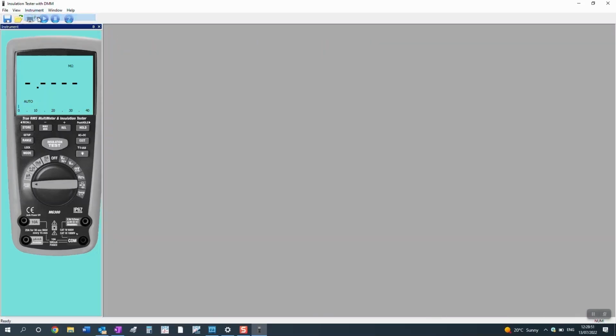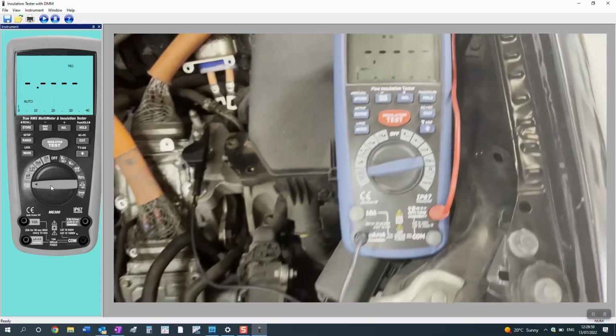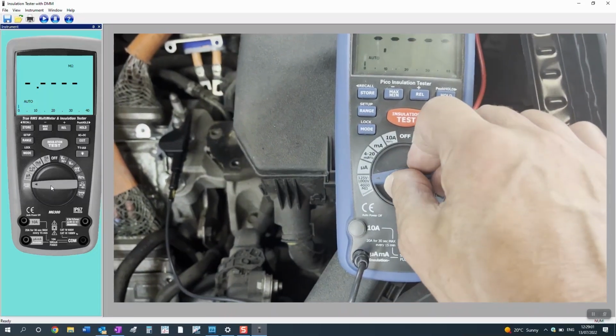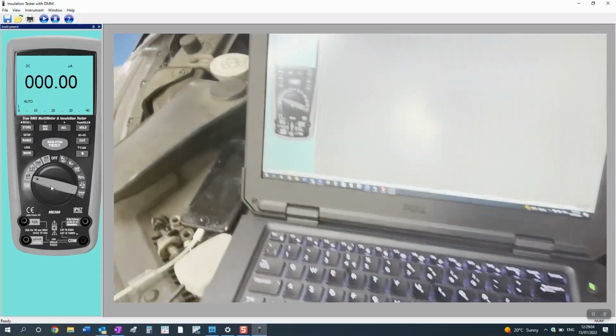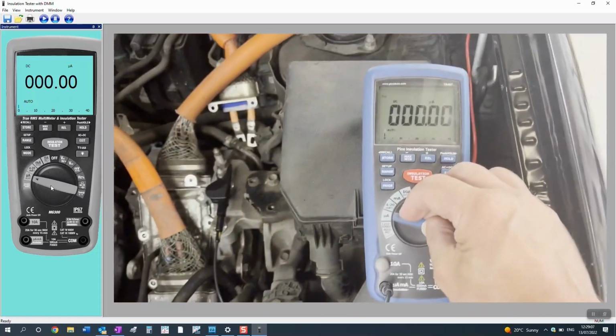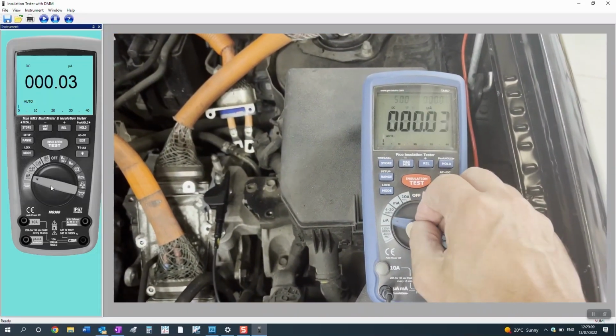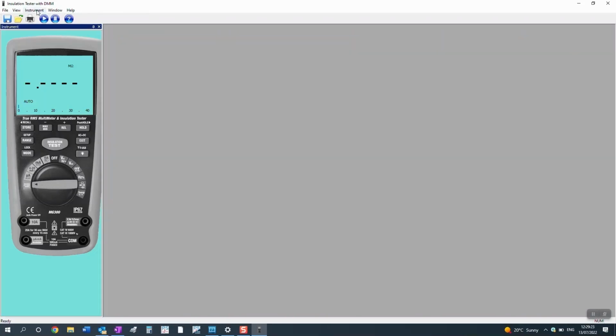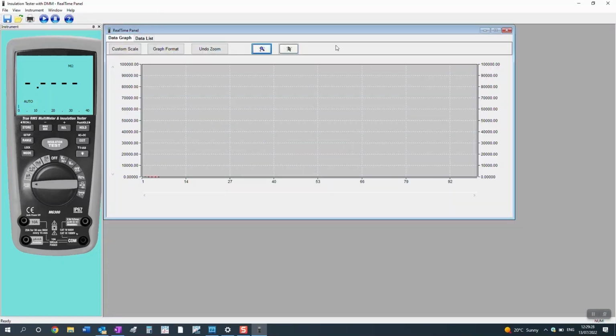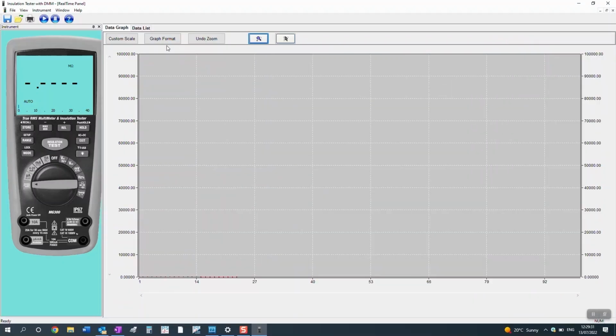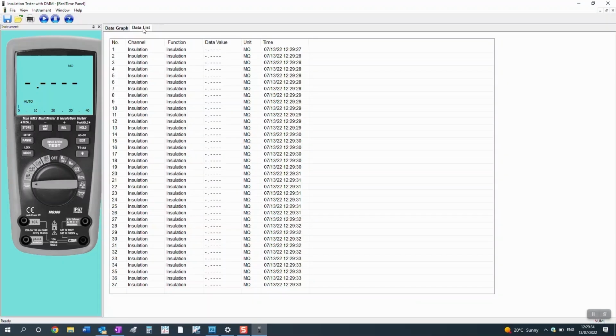We click on instruments, click pair, and we can see now that the meter position in the software corresponds to the meter position on the meter. So if I turn this dial, we should see that change. Let me do that once more. There we are. So we also want the real-time chart instrument, real-time chart recording. There's our sample rate. Let's make this full size, and we'll go for data list. Okay, so at the moment you'll see there that the meter is sending across data.